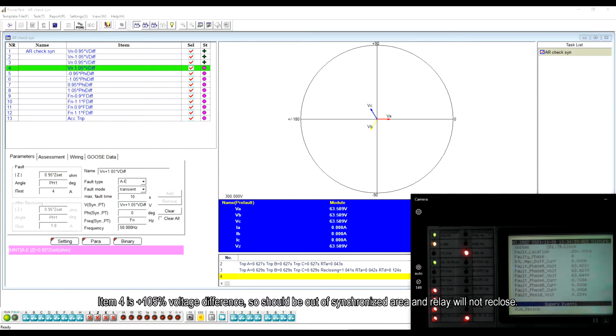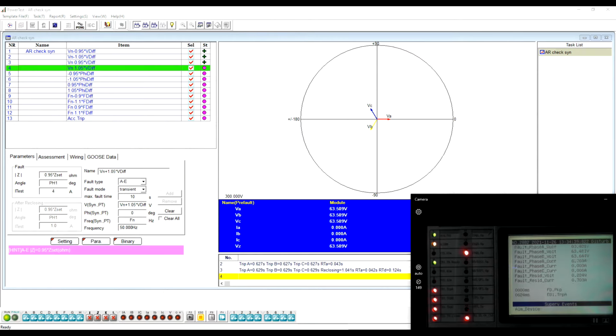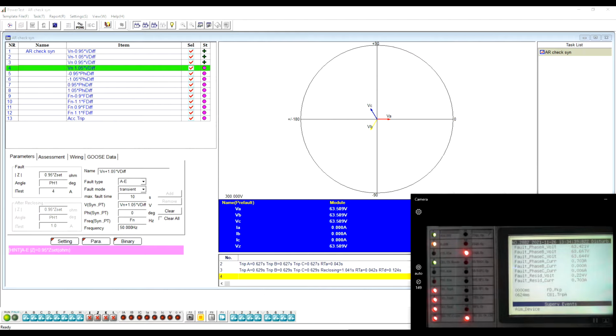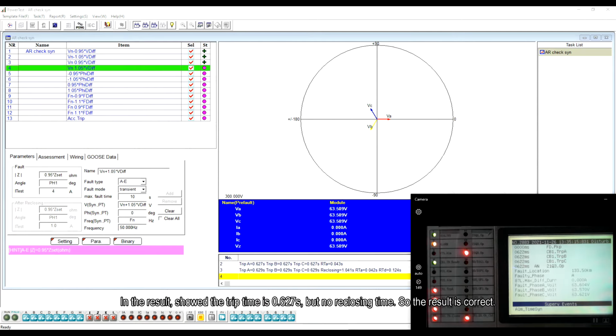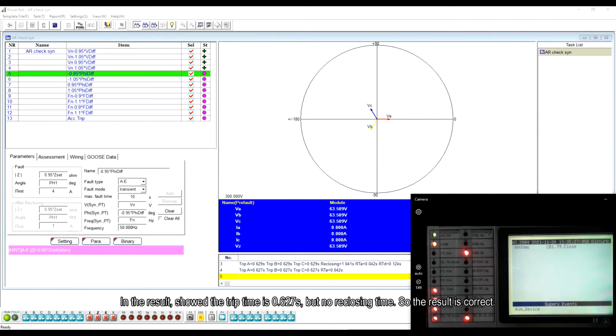Item 4 is positive 105% voltage difference, so should be out of synchronized area and the relay will not reclose. In the result showed the trip time is 0.627 seconds, but no reclosing time, so the result is correct.